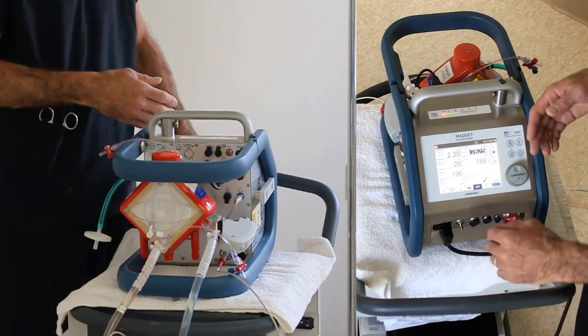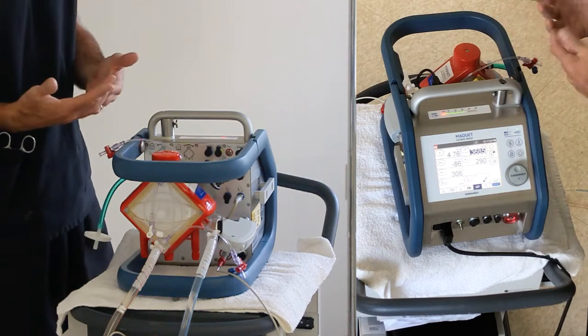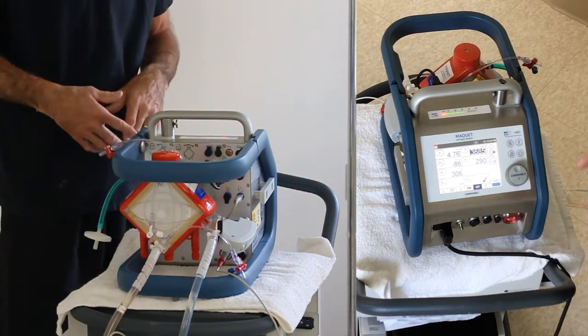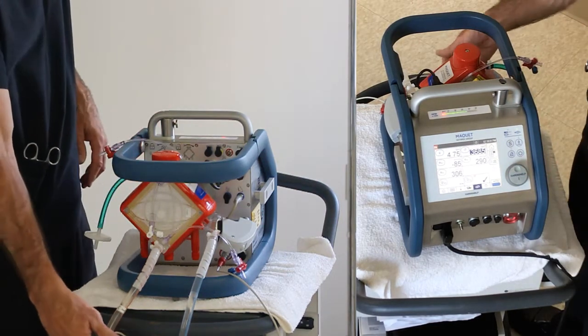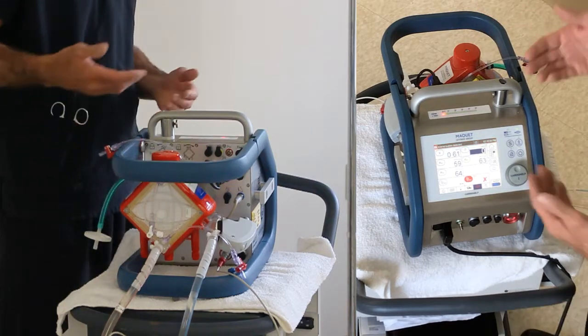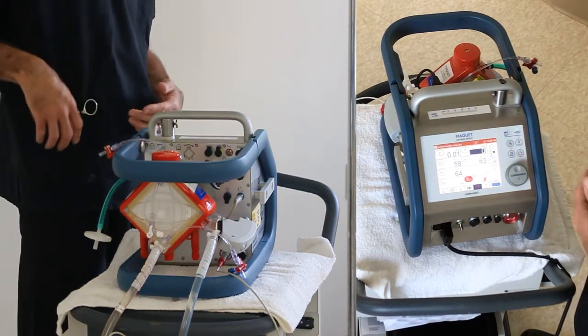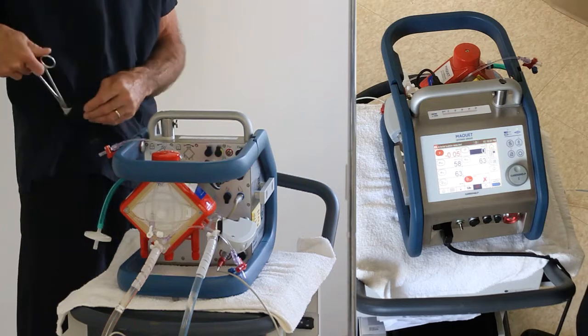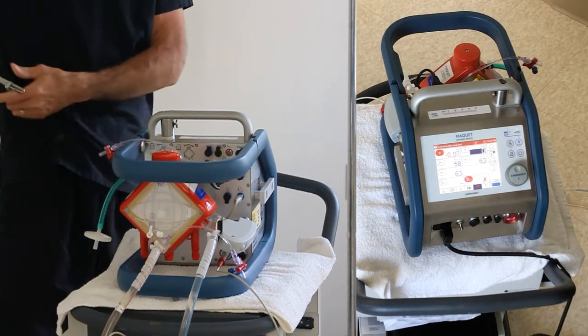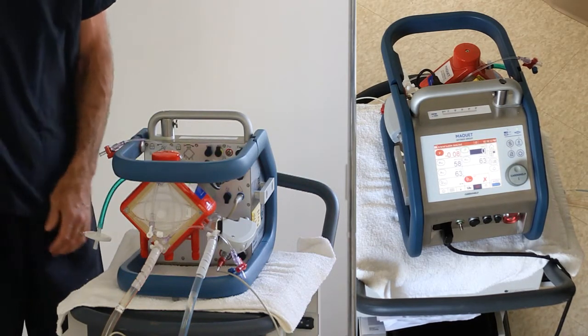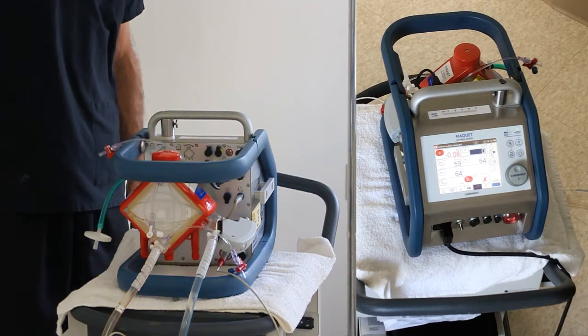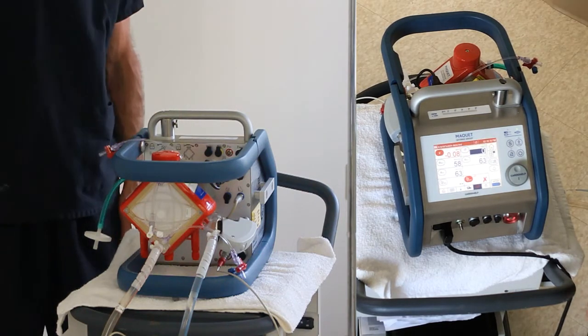So that's the software side of it. What's the clinical side of it? Don't do it that way. What you should do clinically is, if your pump tells you there's a bubble, oh gee, I hear an alarm, my pump says there's a bubble, I should clamp the art line as soon as I can, up near the patient as best I can, in case there's air heading up to the patient.